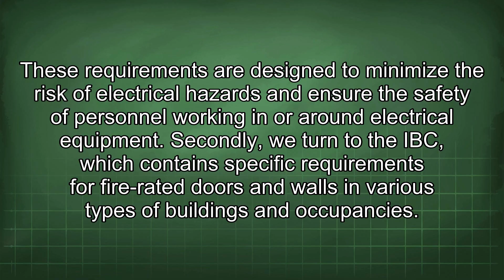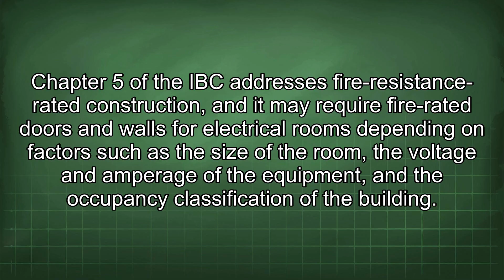Secondly, we turn to the IBC, which contains specific requirements for fire-rated doors and walls in various types of buildings and occupancies. Chapter 5 of the IBC addresses fire resistance rated construction, and it may require fire-rated doors and walls for electrical rooms depending on factors such as the size of the room, the voltage and amperage of the equipment, and the occupancy classification of the building. For example, the IBC may require a 1-hour fire resistance rating for walls separating an electrical room from other occupied spaces.